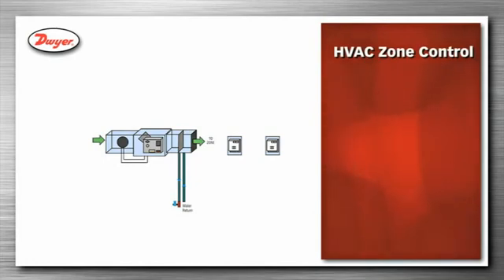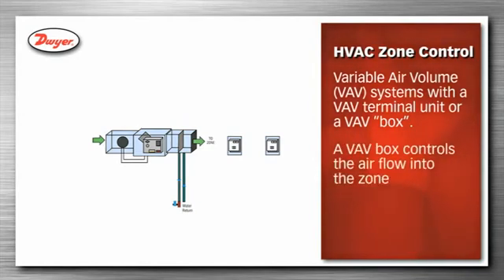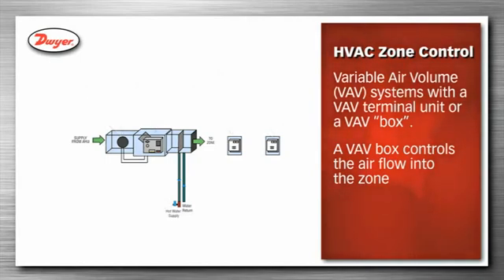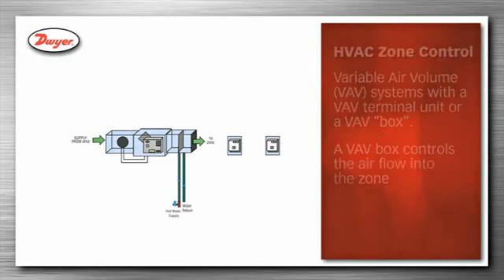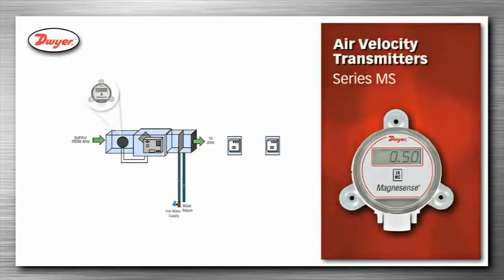Buildings are often broken down into zones for better control of the HVAC system. These zones can have variable air volume, VAV systems, with a VAV terminal unit or a VAV box. A VAV box controls the air flow into the zone, thereby controlling the environment of the zone. Dwyer offers several products used in zone control. Damper actuators, series DD, are used to control the amount of air added to the zone by opening and closing the air duct via a damper. An air velocity transmitter, series MS differential pressure transmitter, is used to monitor the duct air flow. The series MS has square root extraction for direct air velocity indication.